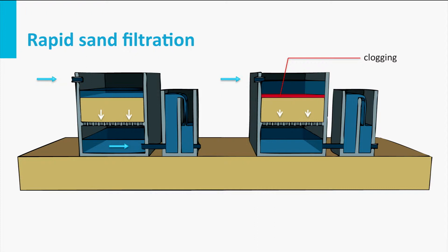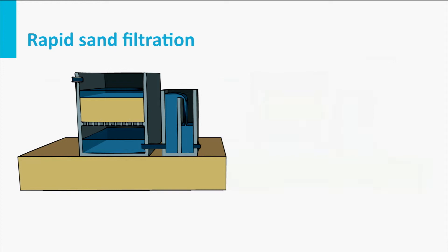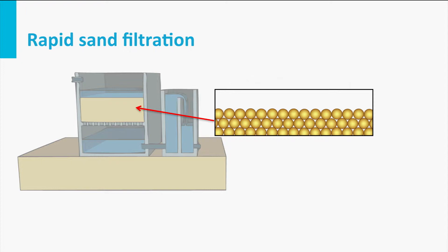During filtration, water passes through a filter bed and suspended solids are removed. Sieving is one of the mechanisms responsible for removal when the suspended solids are too large to enter the pores of the filter bed. In this case, the solids accumulate on the top of the filter bed.